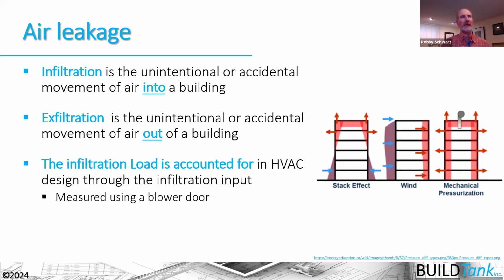And we start gaining more control and predictability of the airflow in those houses. So the infiltration load is accounted for in our HVAC design through a specific input on the software there. And we use this device, a blower door, to be able to measure the infiltration of our houses there. So if you haven't done a blower door on a house that you've worked on, you should consider doing that.